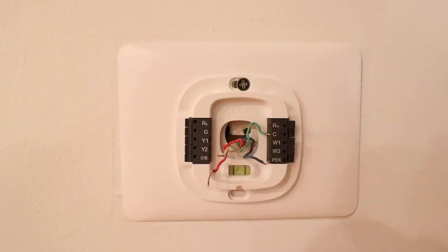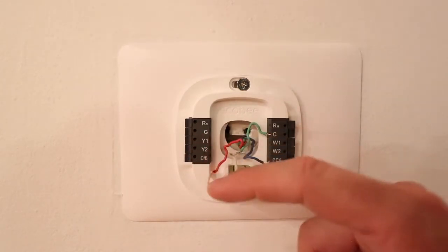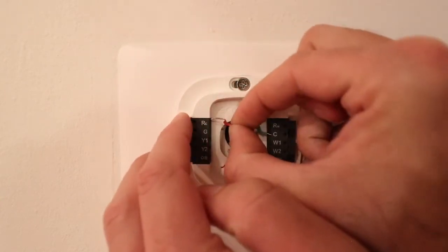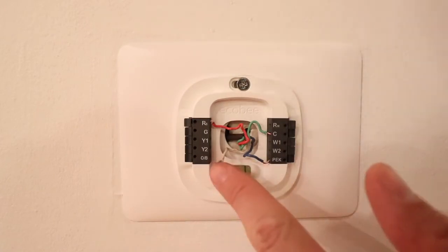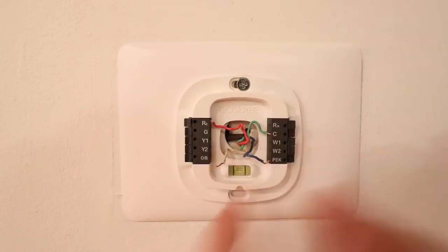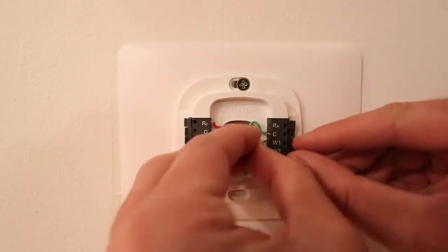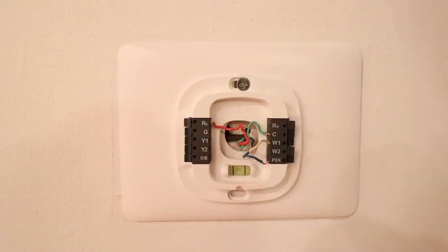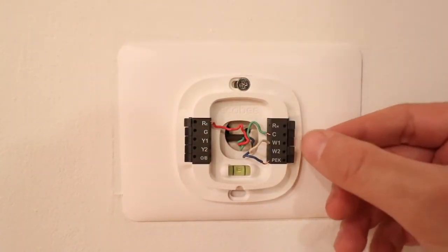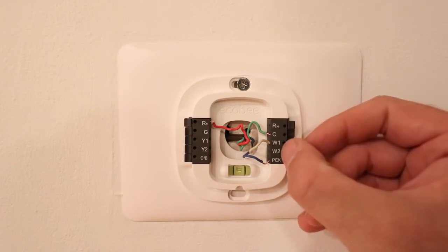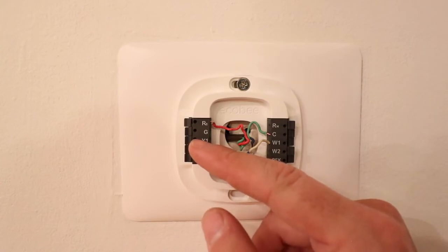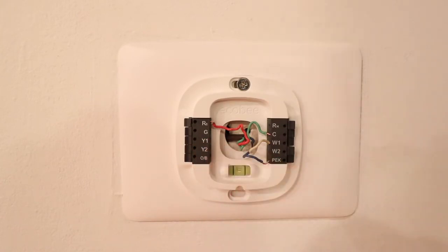For the rest of the wires, you just match those up with the terminal designations on your old thermostat. We take our R wire and put it in the RC terminal, and this white wire goes in the W1 terminal. If you wonder why there's a W1 and W2 and a Y1 and Y2, that's for two-stage heating and cooling systems: W1 is single stage heat, W2 is second stage heat, Y1 is single stage cooling, Y2 is double stage cooling. OB is for heat pump, G is for fan, the R terminals are for power, the C wire is the common wire, and the PEK is the power extender kit.